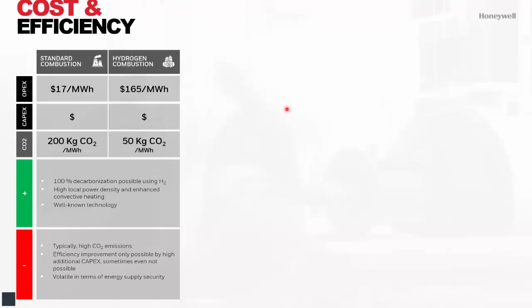It's still difficult to increase efficiency in standard combustion systems. You need to invest in heat exchangers, and with this you get other downsides: the control gets more complex, you might need insulated air lines, and recuperative burners are also not a cheap thing to do. This point applies more toward Europe, we learned it the hard way: energy supply can be volatile, especially at the moment for Europe.